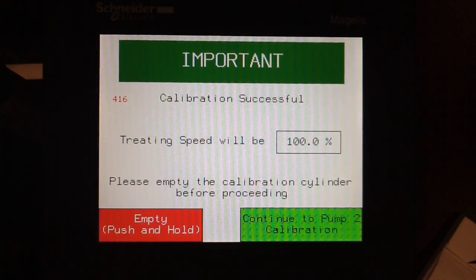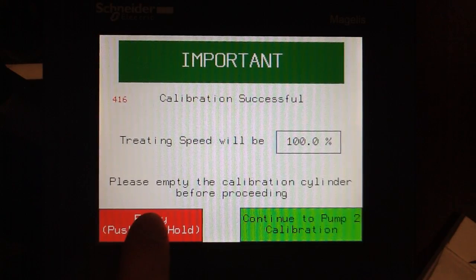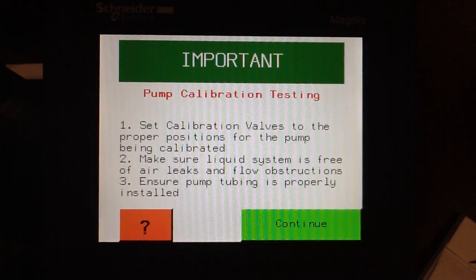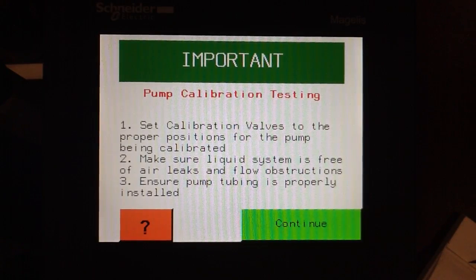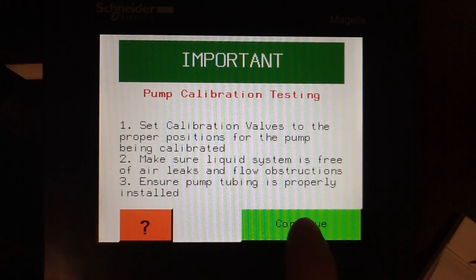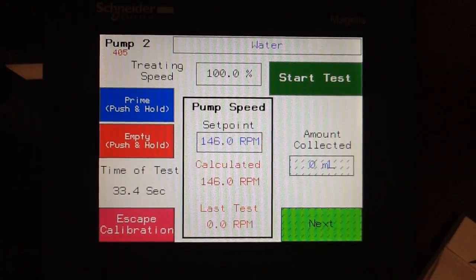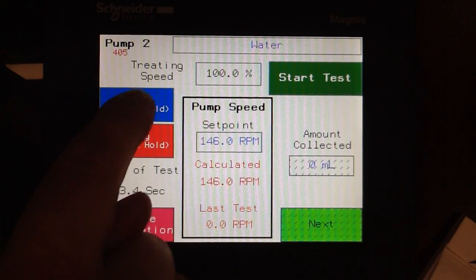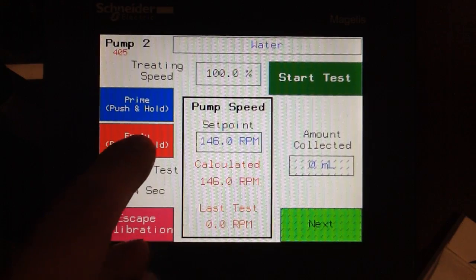Before continuing to pump two, we must empty the cylinder completely and continue to pump two. Again, an important screen pops up asking us to change the calibration valves to the proper position, making sure the liquid system is free of air leaks and obstructions, and ensuring the pump tubing is properly installed. Select Continue. We now repeat the process for pump two, priming until all of the air is out of the cal cylinder, then emptying back down to the zero mark.